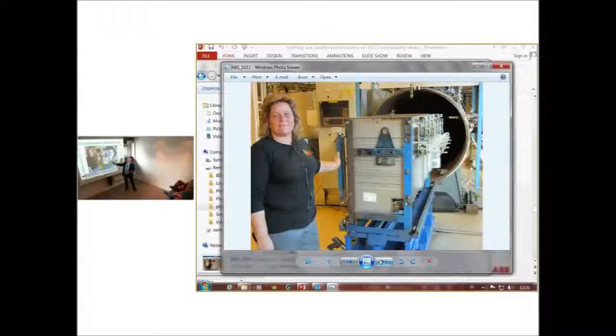Actually, we did a test for this in Belgium. The Belgian authorities, Synergrid, if you check www.synergrid.be, you can look into approved switchgears in the Belgian network. And they have a laboratory called Laborelec. They asked us to deliver 8 units. They heated all 8 units up to 40 degrees and then measured SF6 leakage.